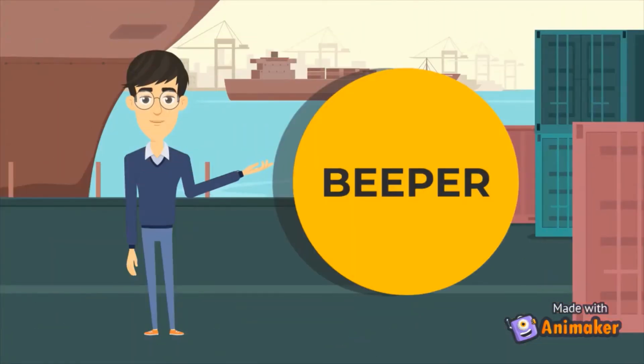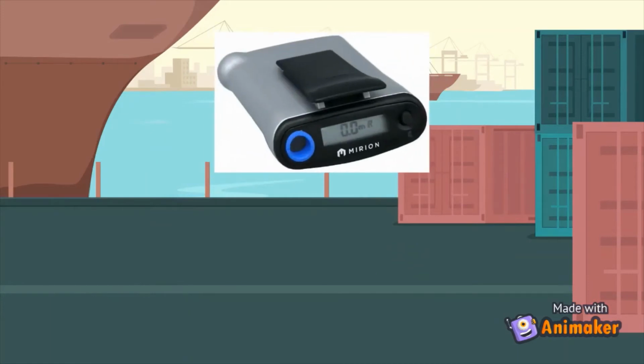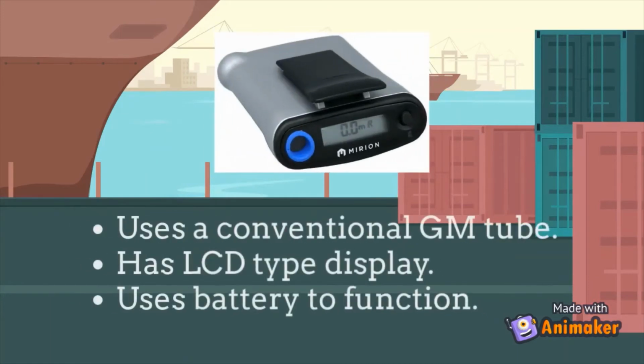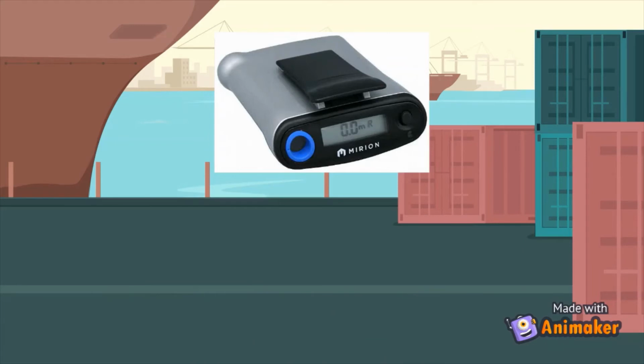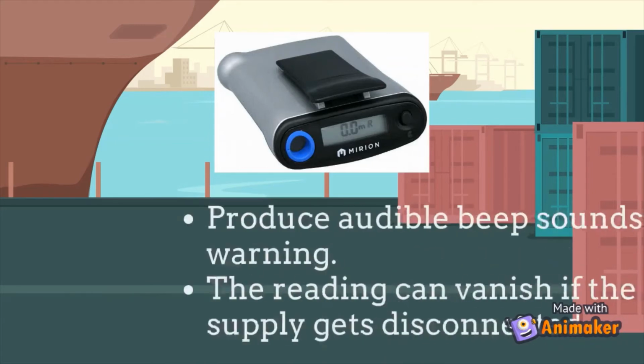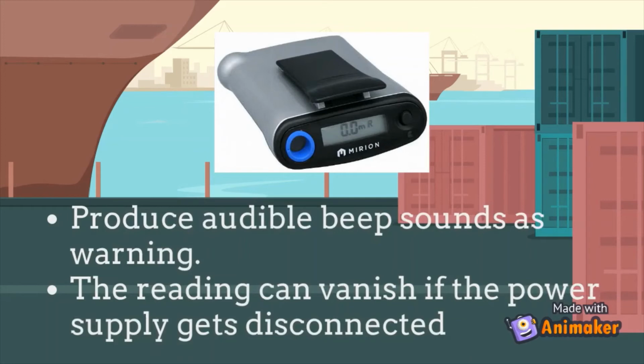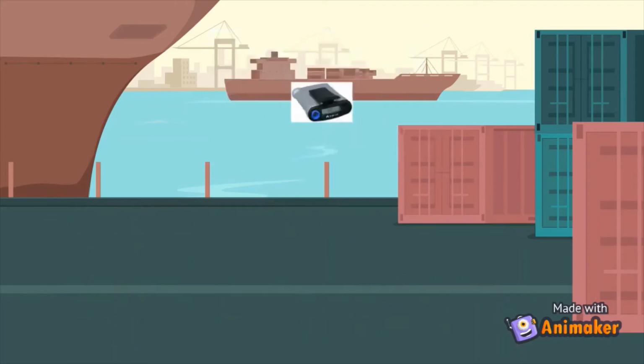The third personal dosimeter is the beeper. The beeper uses a conventional Geiger-Muller tube and has an LCD type display to display the dose rate. It uses a battery as power supply to function. Like its name, the beeper will produce an audible beep as a warning when the radiation dose exceeds a certain value. However, the reading of the beeper can vanish if the power supply gets disconnected.